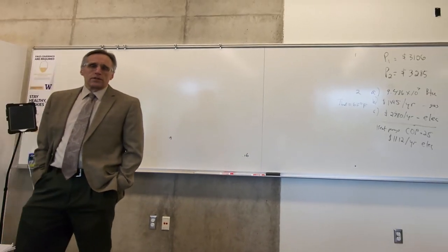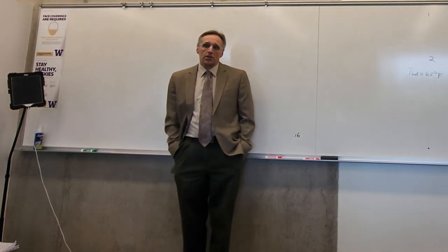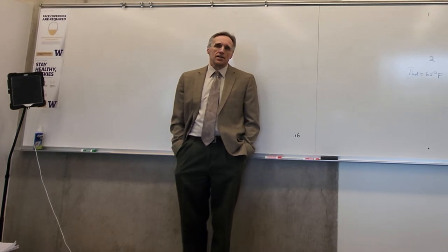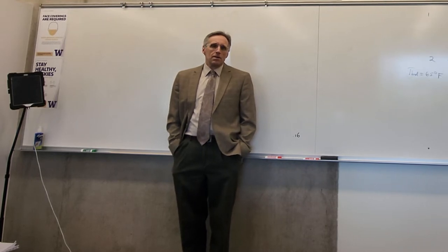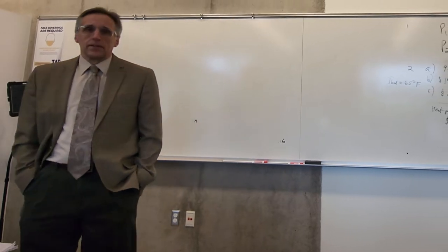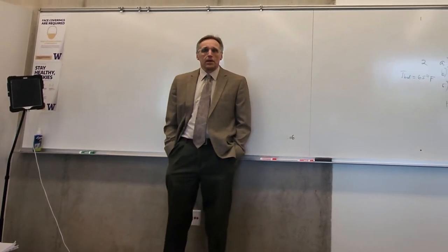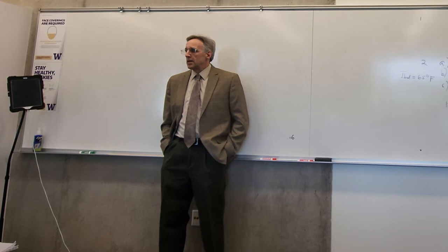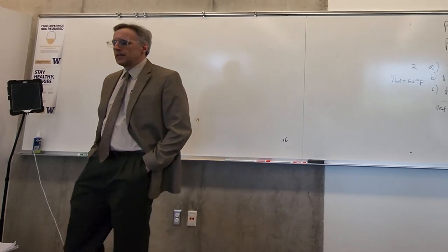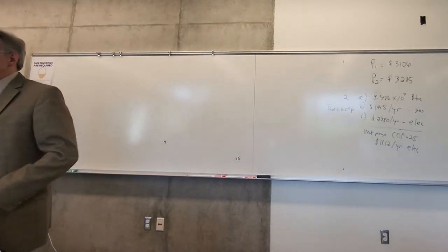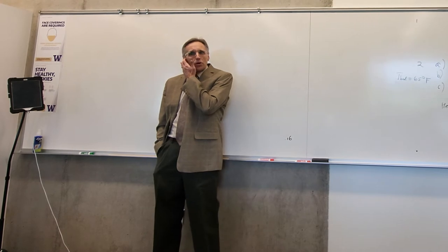To heat water up to 160 degrees, you would have to have R410 near its critical point. You have to have 600 psi in the condenser. That's a really high pressure. I don't know how they're doing that. I thought about it, and I don't know how they do it. There must be something I'm missing. I haven't worked with water source heat pumps. I probably need to spend some time studying those and bringing that into my teaching, because we're starting to see a shift toward more heat pumps, but they're still not widely used to the point where engineers have a lot of experience working with them.